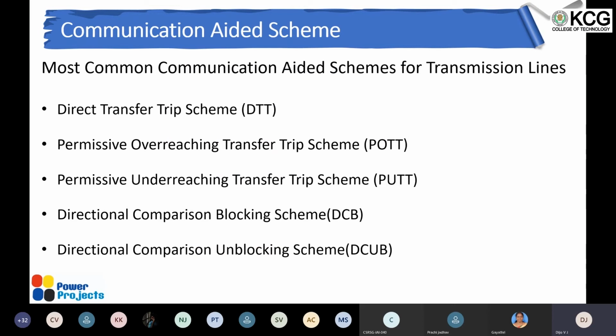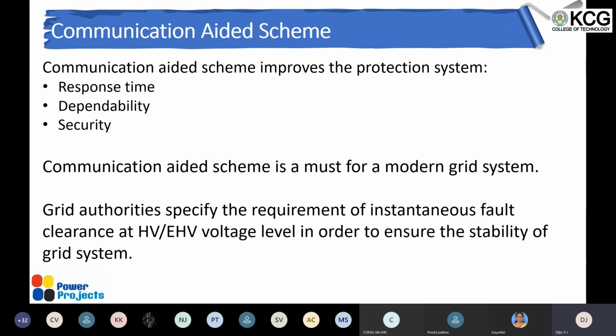There are a few tripping schemes, like the direct transfer trip scheme, which we have just now discussed, and other tripping schemes are listed down. I'm not going into the detail of that. It's also communication based, with the permissive from the local end. Maybe for the time being it's not very important. The communication aided scheme improves the protection system. Just to have an understanding, we have already seen it: the response time is improved. Earlier it was taking around 400 milliseconds, but now it is reduced to close to 100 milliseconds. That's what we have seen.